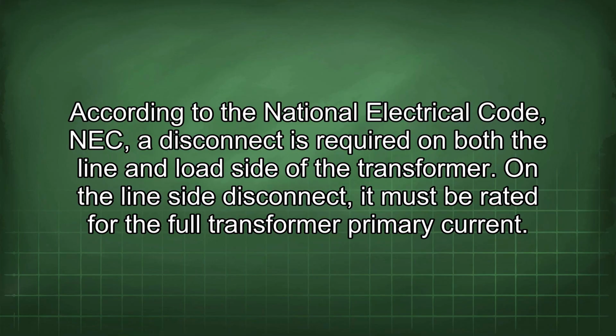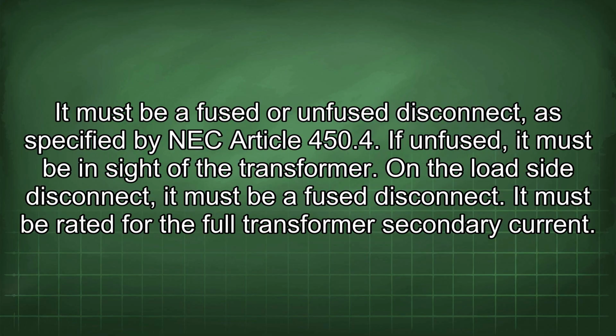According to the National Electrical Code, NEC, a disconnect is required on both the line and load side of the transformer. On the line side disconnect, it must be rated for the full transformer primary current. It must be a fused or unfused disconnect as specified by NEC Article 450.4. If unfused, it must be in sight of the transformer.